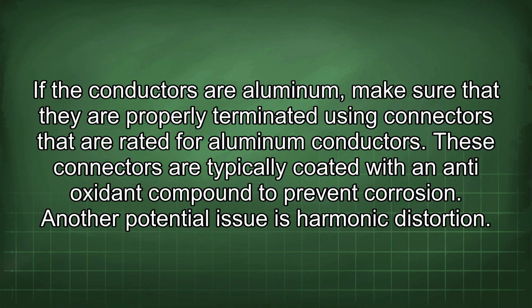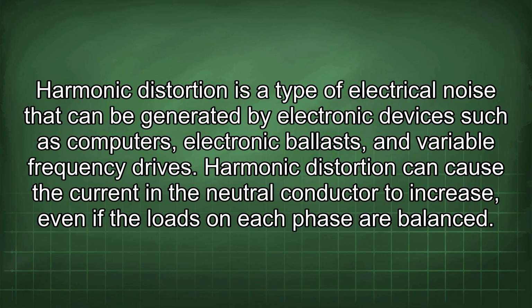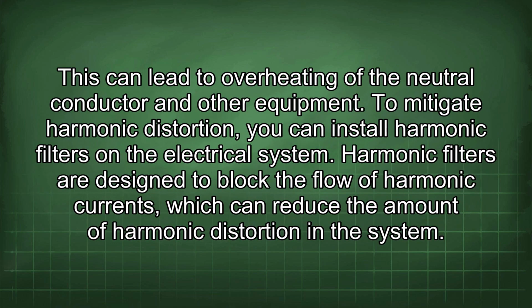Another potential issue is harmonic distortion. Harmonic distortion is a type of electrical noise that can be generated by electronic devices such as computers, electronic ballasts, and variable frequency drives. Harmonic distortion can cause the current in the neutral conductor to increase, even if the loads on each phase are balanced. This can lead to overheating of the neutral conductor and other equipment. To mitigate harmonic distortion, you can install harmonic filters on the electrical system. Harmonic filters are designed to block the flow of harmonic currents, which can reduce the amount of harmonic distortion in the system.